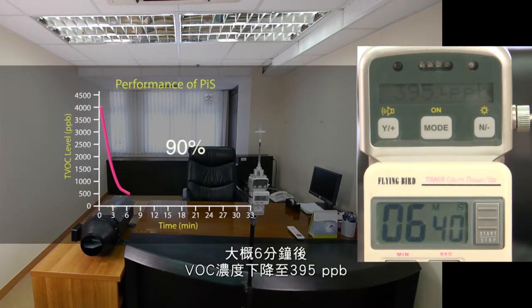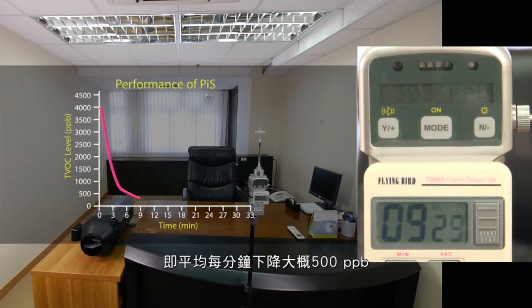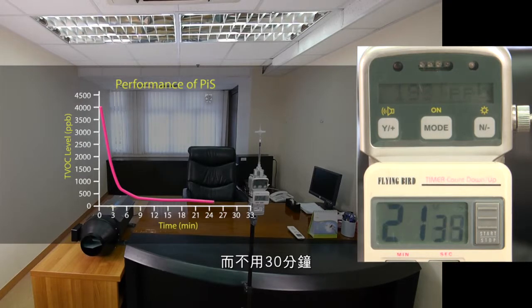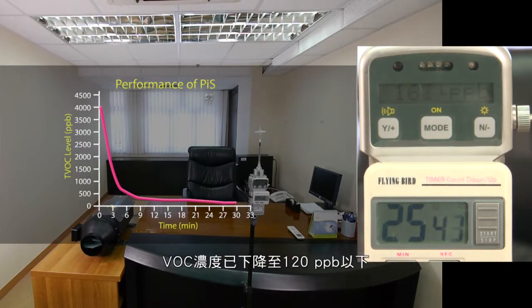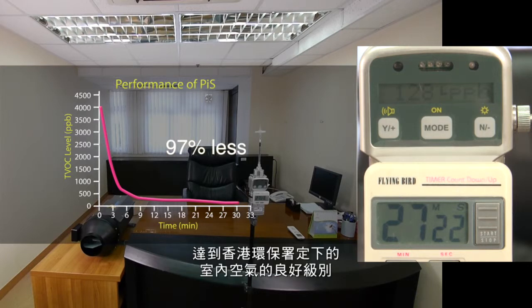After 6 minutes, the TVOC concentration is lowered to 395 ppb, which means the concentration has dropped at an average rate of 515 ppb per minute, and in less than 30 minutes, the concentration has dropped to below 120 ppb. This reading falls into the good class level for indoor air set by the Hong Kong Environmental Protection Department.